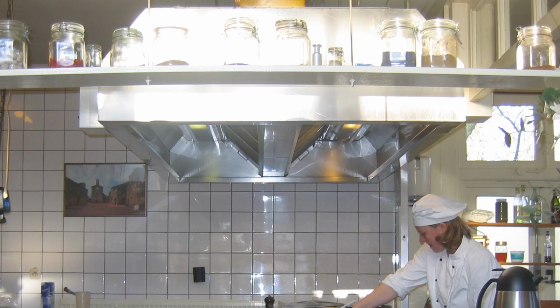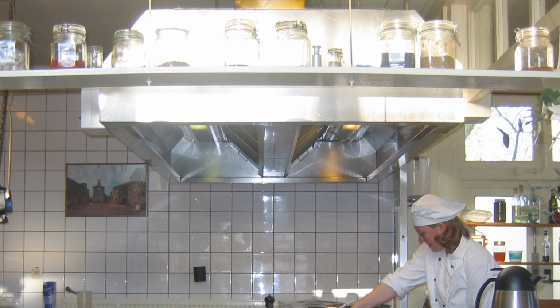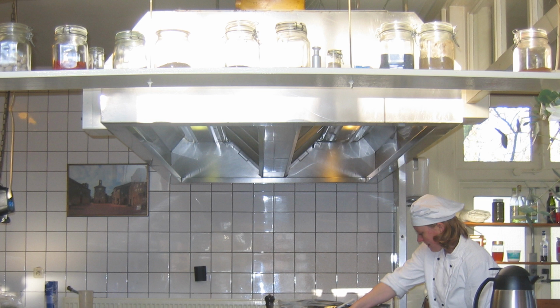For many kitchens, the recommended overhang for a range hood is no less than 3 inches. However, for the most effective capture and containment, there should be a 6-inch overhang on the front and sides of the appliance beneath the hood. By doing this, the range hood has twice as much coverage for capturing and containing harmful emissions.